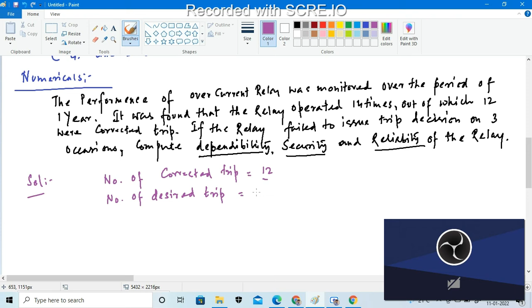So the number of desired trips is 12 plus the three occasions, so 12 plus 3 will be 15. Now the percentage of dependability is equal to the number of correct trips divided by the number of desired trips, into 100. So that is my formula. Putting in the values, the number of correct trips is 12 and the number of desired trips is 15, into 100. That is equal to 80%.